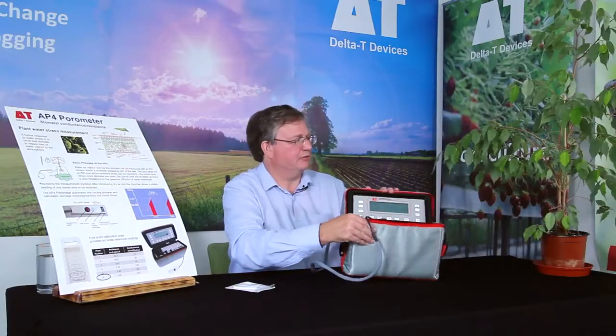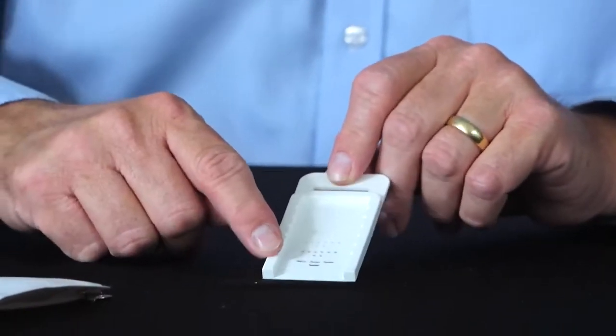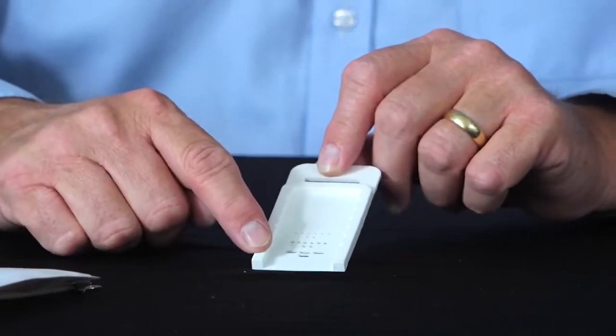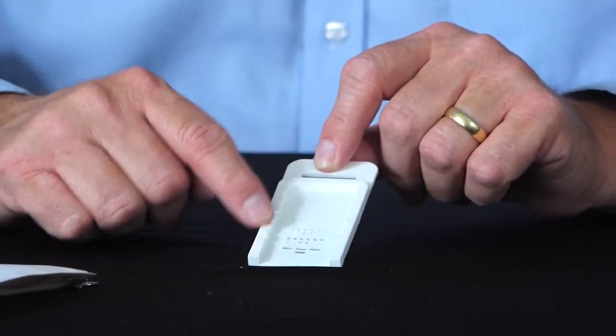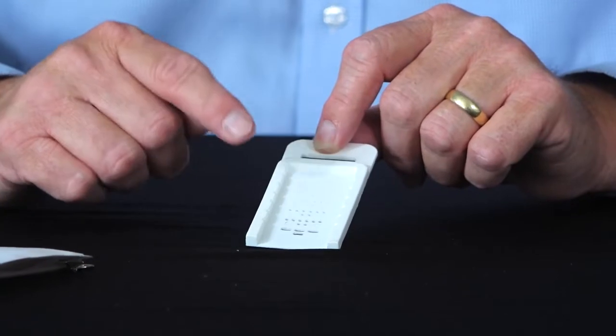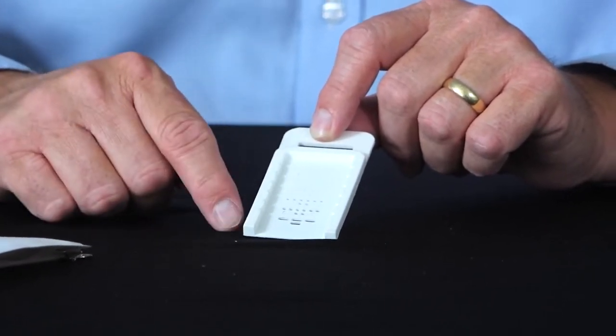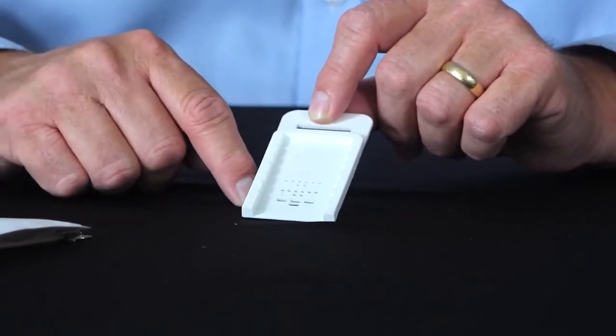To calibrate the AP4, we use the calibration plate I removed earlier. This has a configuration of 6 sets of holes. These range from very large to smaller. So these are open stomatal state to very closed stomatal state. So we can generate a 6-point calibration curve for the Porometer.